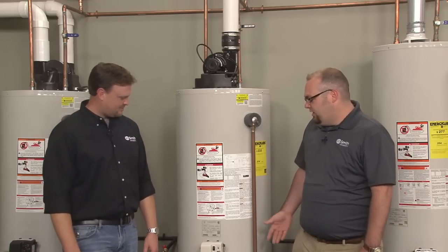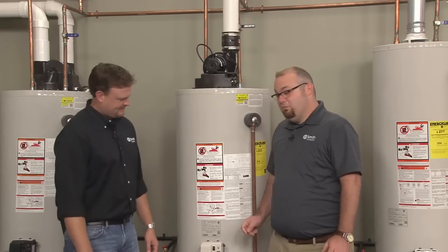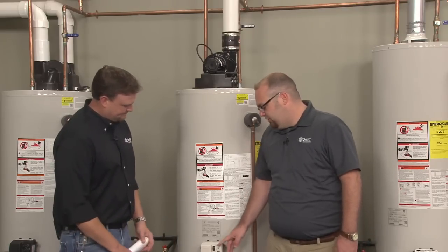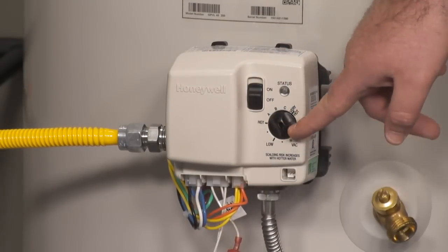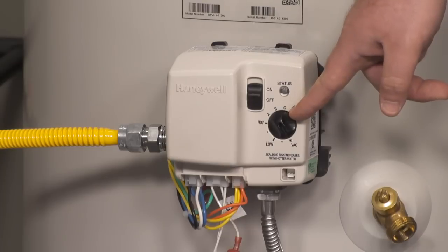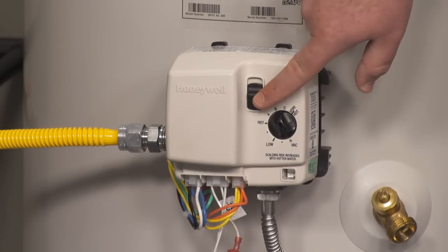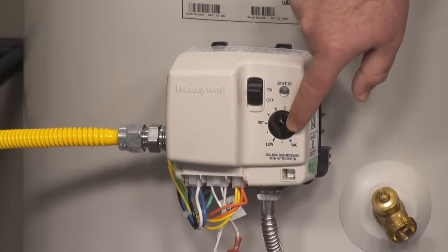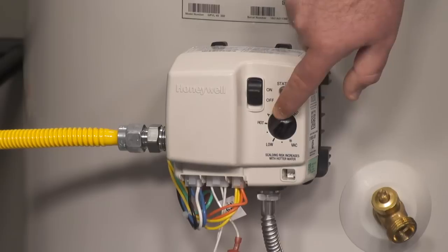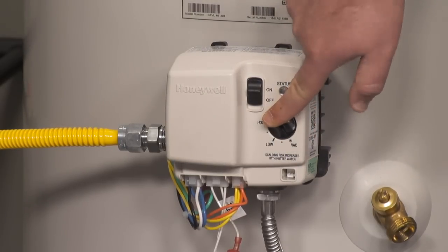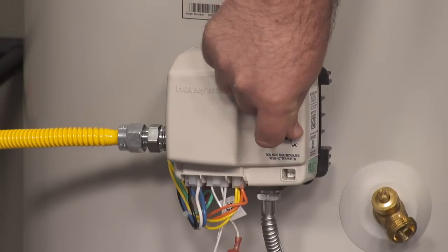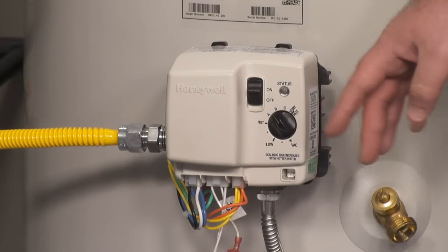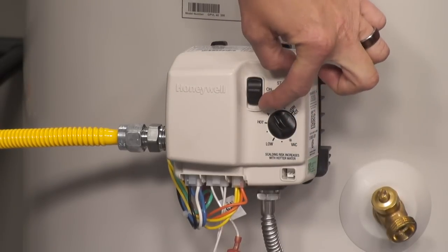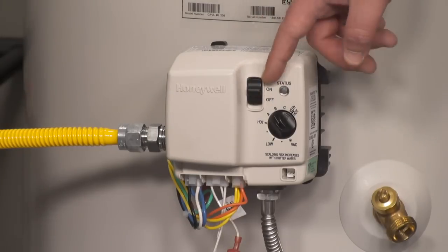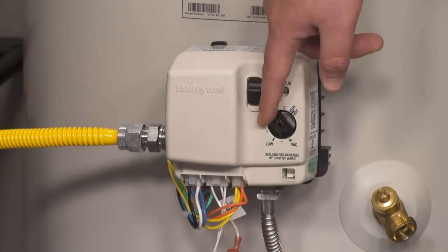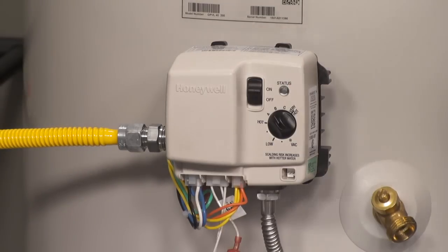Okay, all right. So the reset procedure is pretty simple, but you have to do it a certain way. It's nothing too involved. So turn the heater off. Turn the temperature knob all the way back down to the vacation setting. So I'm going to turn it all the way down, right? Okay. I'm going to turn the power back on, and then wait about 3 seconds, I'm going to turn the temperature up past hot. I'm going to turn it back down all the way. I'm going to turn it back up past hot again, and then it should reset. Okay. So once you turn it past hot, go back to vacation, and then just set your temperature. Yes, but it's just always all the way down, turn it up past hot, all the way back down, up past hot, and then it should reset as long as everything's good.